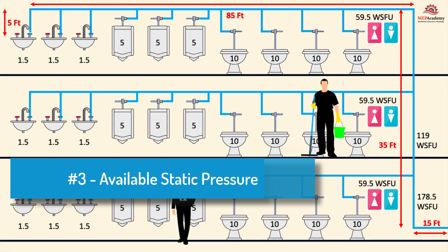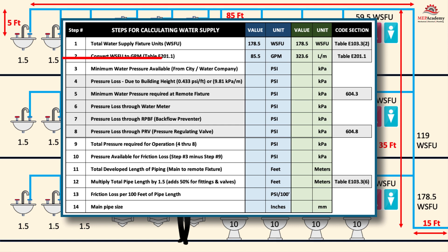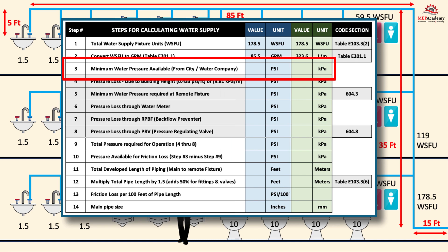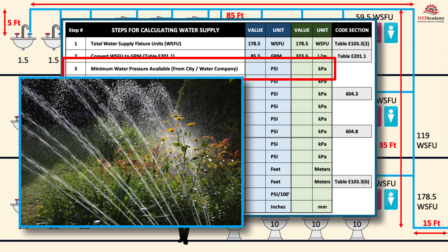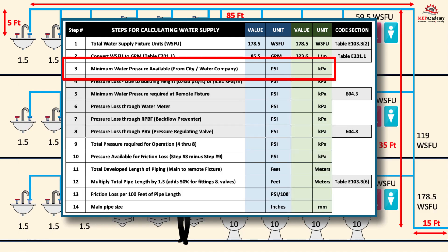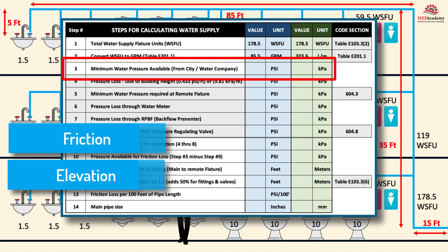Step 3: Obtain Minimum Daily Static Pressure. The available static pressure in PSI or kPa at the water meter or source is provided by the city or local water authority. The minimum pressure is used in the calculation to ensure that during peak water usage — usually summer, when landscaping systems are maximized and water-based cooling systems are at peak — sufficient pressure is available to overcome all system losses due to friction and elevation so that plumbing fixtures operate properly.